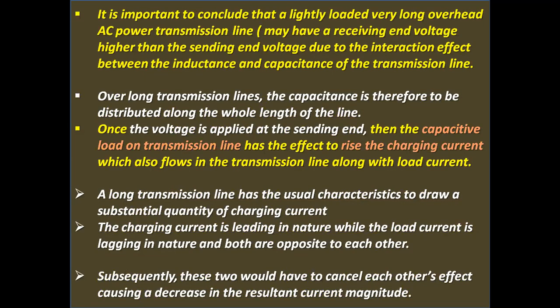It is important to conclude that a lightly loaded, very long overhead AC power transmission line may have a receiving end voltage higher than the sending end voltage due to the interaction effect between the inductance and capacitance of the transmission line. Over long transmission lines, the capacitance is therefore distributed along the whole length of the line. Once the voltage is applied at the sending end, the capacitive load on the transmission line has the effect of raising the charging current, which also flows in the transmission line along with load current.